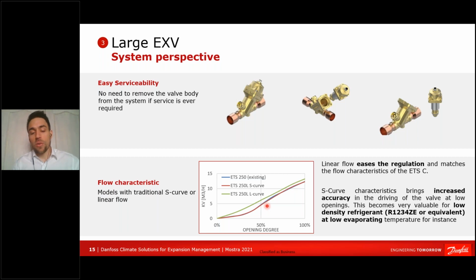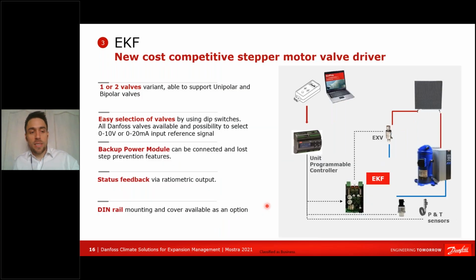But if you're using a multiple circuit chiller or any multiple circuit system, a heat pump for instance, and you have a Colibri on one circuit and you need an ETS Large on the other circuits, then it could be important to have a matching characteristic. As the Colibri is linear, the ETS Large should be linear. It's much easier for the main controller to do all the job. Then you don't have to have a specific algorithm for each circuit. You can probably mimic the algorithm you have for one circuit on the other one. This was for the valve.